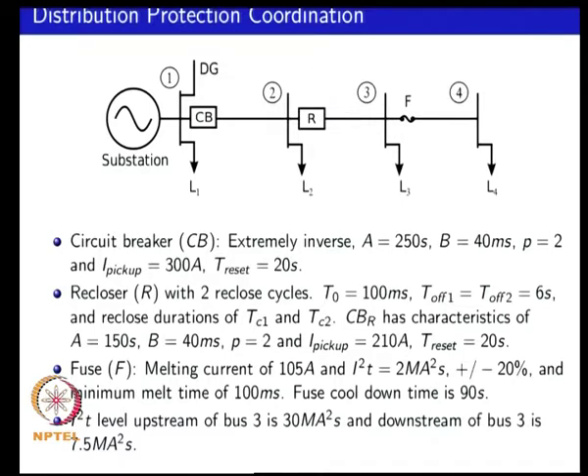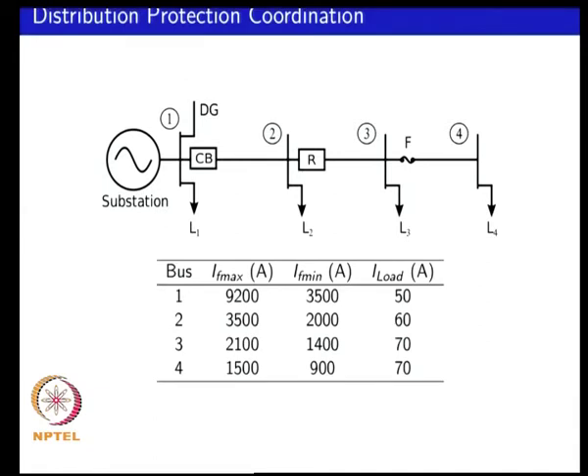We plotted the trip time versus current characteristics of such devices, including the nominal fault current ranges and load current ranges. We looked at the properties of individual devices and the time over-current coordination between upstream and downstream devices. We also checked whether we have backup protection in case one protective device fails, and whether there are adequate time margins in the protection settings.